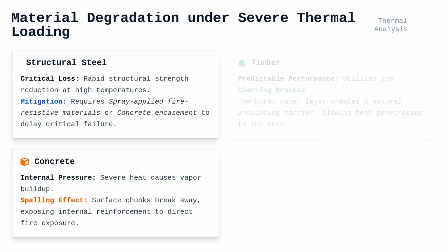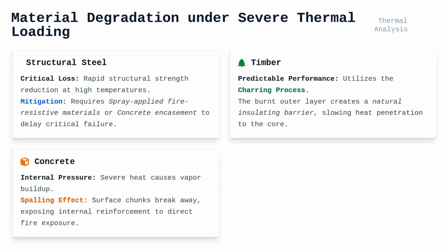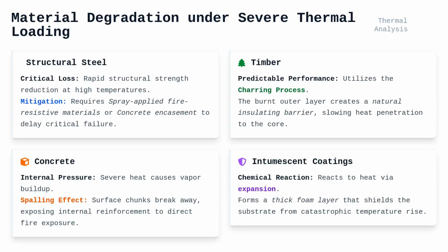Timber, while combustible, provides predictable performance through charring, where the outer layer burns away to create a protective, insulating barrier that slows the progression of heat into the remaining structural core. Intumescent coatings provide another layer of defense by reacting to heat through expansion, creating a thick, insulating foam layer that shields the substrate from the rapid temperature rise that would otherwise result in catastrophic failure.